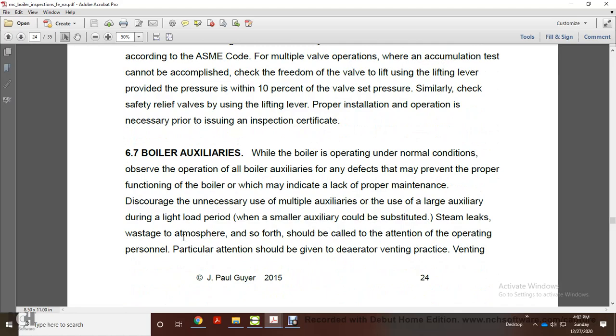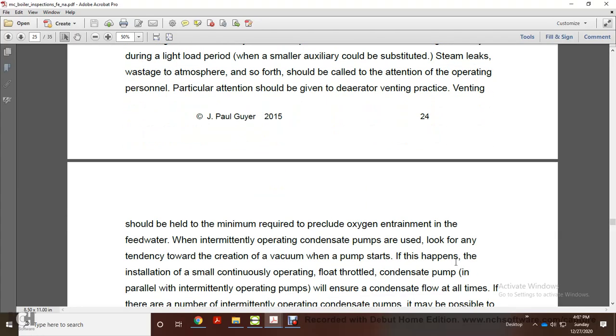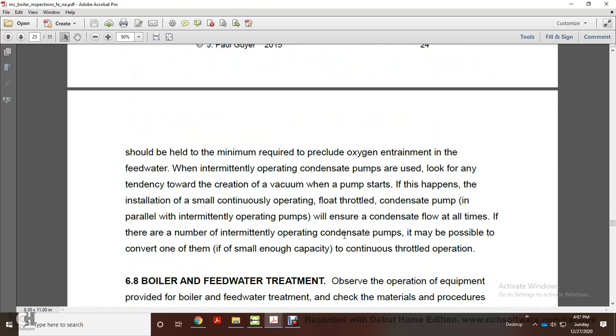If the boiler is operating under normal conditions, observe the operation of all the boiler auxiliaries. Defects that prevent the proper function of the boiler may indicate lack of proper maintenance. Discourage unnecessary use of multiple auxiliaries during light load. When a smaller auxiliary is substituted, steam wastage to atmosphere and so forth can be reduced. Attention to operating personnel: particular attention should be given to deaerator venting practice. Venting should be made at the minimum required pressure to preclude oxygen entrapment in the feed water.